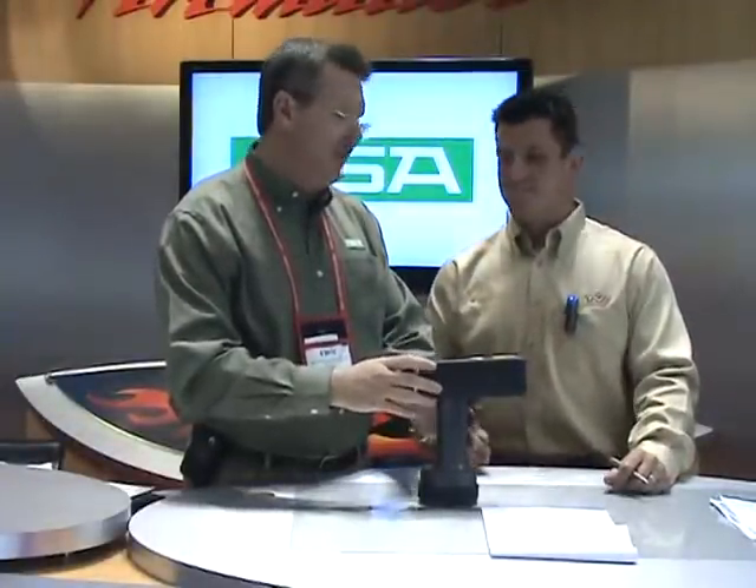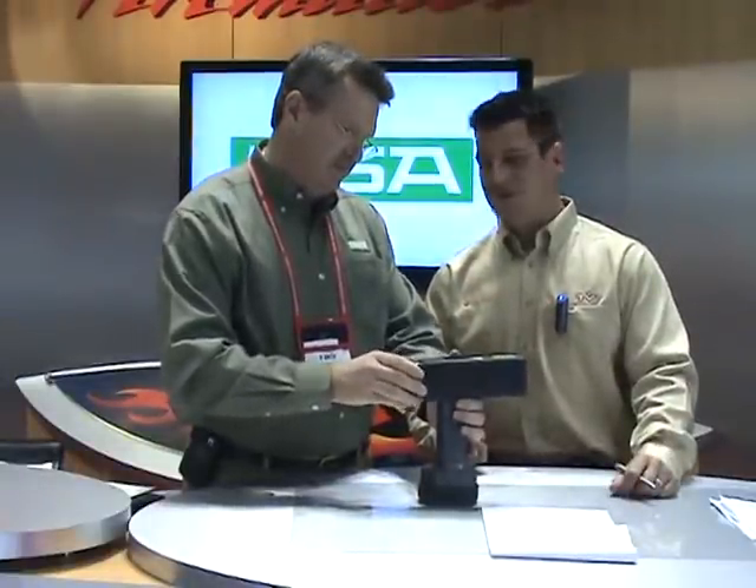What are we running on here? I noticed it's powered and sampling right now. This runs on lithium ion batteries, which gives you eight hours of operation. When you're out in the field and need to do a rapid change, it's as easy as sliding a battery out and sliding another one in. Looking at this battery, if you've seen any of our other MSA products, they all run on a similar lithium ion battery — very darn close to the same one. You can recharge this and have the unit ready on standby at any time. You can run it on one battery or two batteries at once, and you can slide one out and slide another one in without even turning the instrument off.